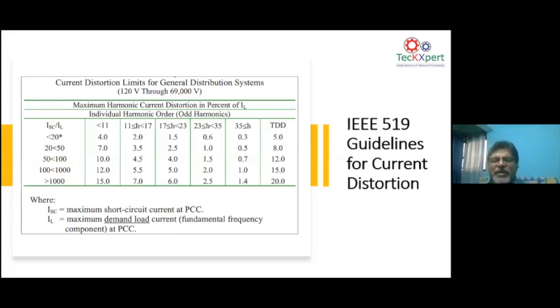And then there is the IEEE standard that talks about how you define the harmonic voltage distortions. And when it comes to current distortion, the current distortion permitted is according to the fault level at a particular point. If the fault level is very high at a point, that means the network is strong enough to withstand higher harmonic current distortion. So according to the IEEE, the ISC by IL, that means the higher the short circuit level, the lower the impedance. That means if somebody injects harmonic currents, the voltage drop on the impedance will be lesser. That means your network voltage distortion also becomes lesser. That is why the ISC by IL concept is used in IEEE 519. So that is the consolidation of whatever I just discussed before.